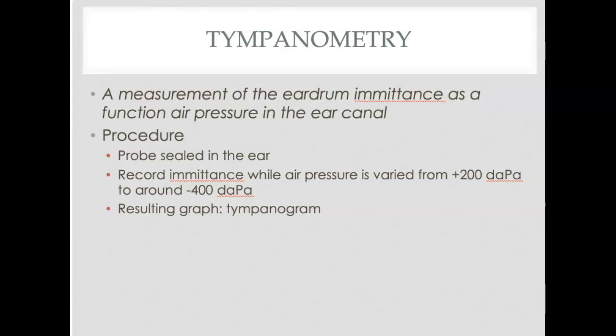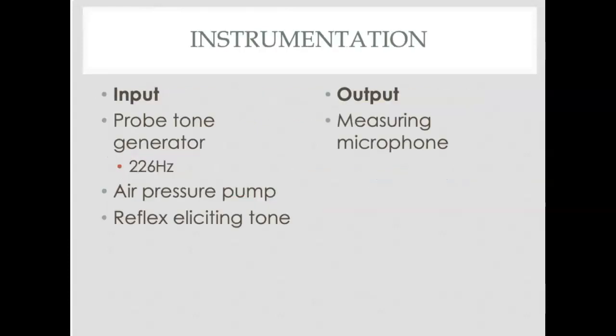What we do is we put the probe in the ear, and it's sealed and has to be sealed so we can maintain the air pressure. Then we record this admittance from plus 200 to minus 400 decapascals as that unit of measure, and the resulting graph is called a tympanogram.